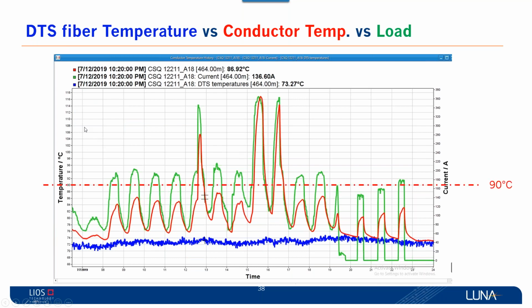As mentioned, we are looking at 90 degrees Celsius. Every time they go up to 220, 250 amp, automatically they trigger that. So what's now important is that during distribution operation, they sometimes have emergency situations where they need to use the line anyway, because they need to reroute the load from one circuit to another. Another circuit might be in maintenance, so this line has to be used.